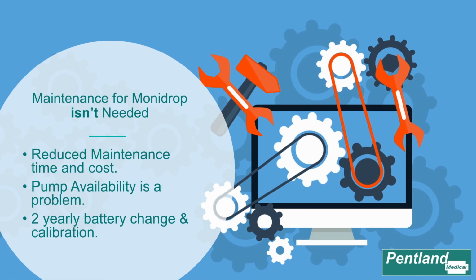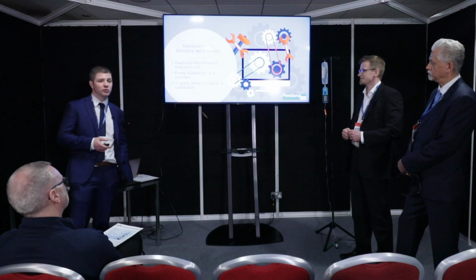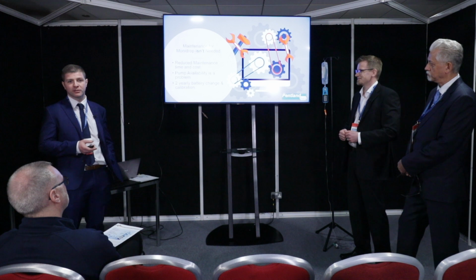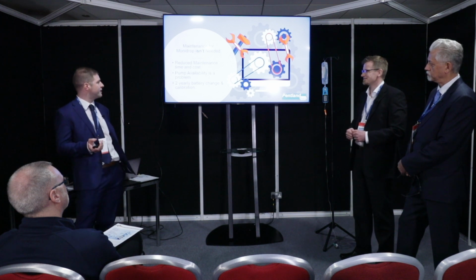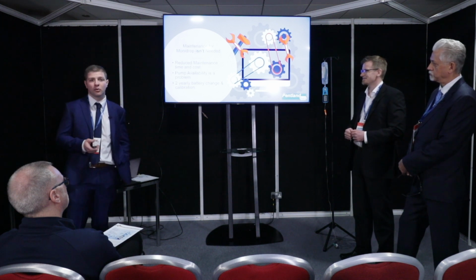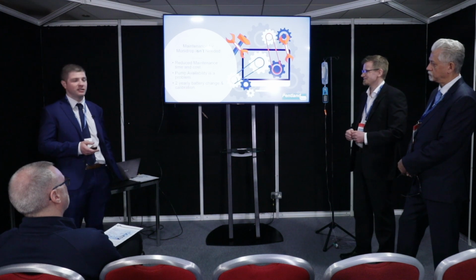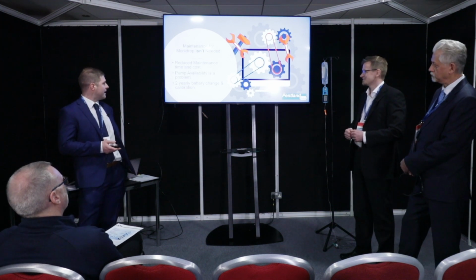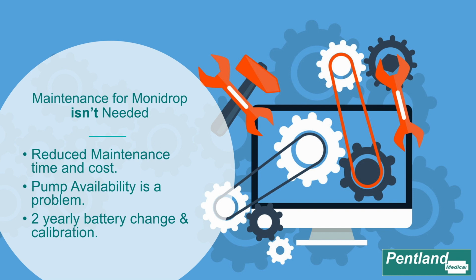So as well as savings on consumable costs, we can also cut down on maintenance required just by cutting down on overall pump usage in the hospital. Pump availability is also a big problem for many hospitals due to the frequency of pumps breaking down and also the cost of new pumps being prohibitive for many NHS trusts. Monidrop is very low cost and low maintenance by comparison. It only requires a battery change and calibration every 2 years.